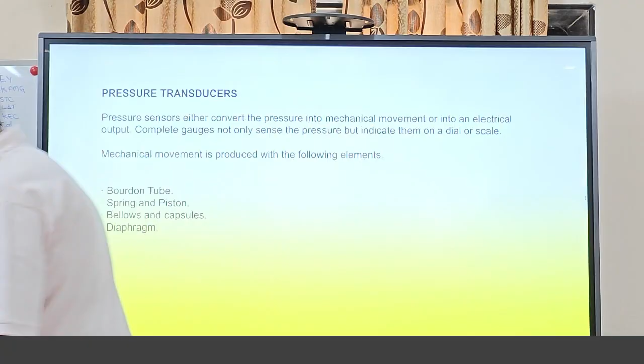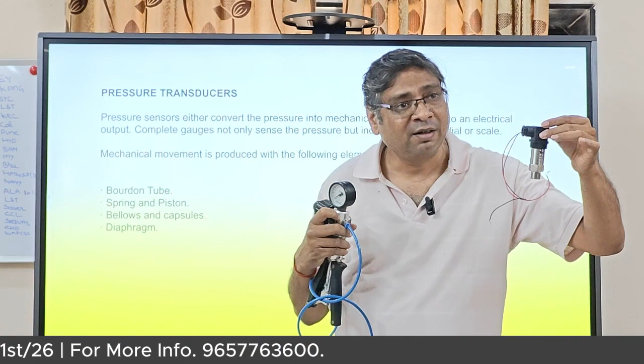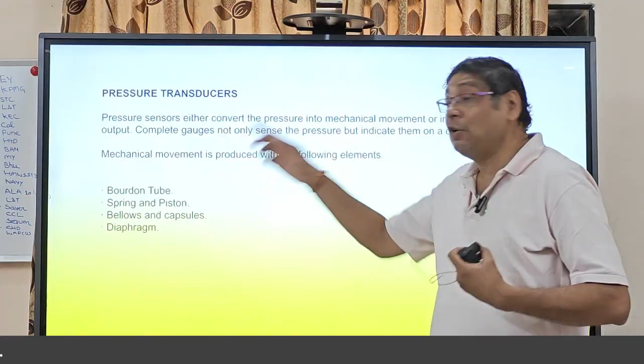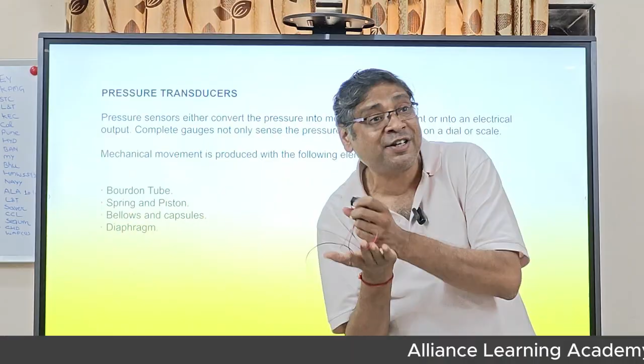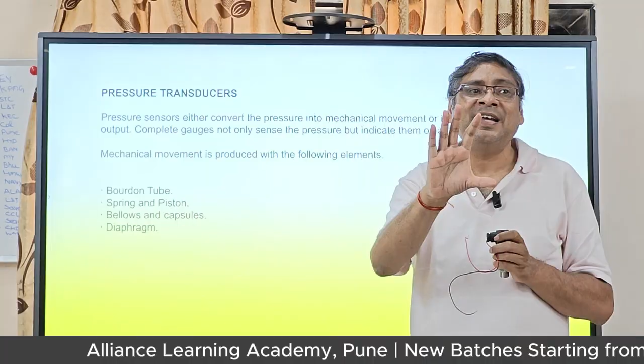Okay. Now you go to the second line. That line shows an electrical output. What you are seeing here is a pressure transmitter. That was a gauge, this is a mechanical gauge, and this is electronic instrumentation. Now what is it saying? The mechanical movement. Now the sensor part: the sensor senses the physical quantity, here the pressure. These are the things that will sense. After sensing, they give either the electrical output or the mechanical movement. In the case of gauges, they give the mechanical one: the Bourdon tube is flattened, and with the pointer and gear assembly it shows the reading on the calibrated dial.